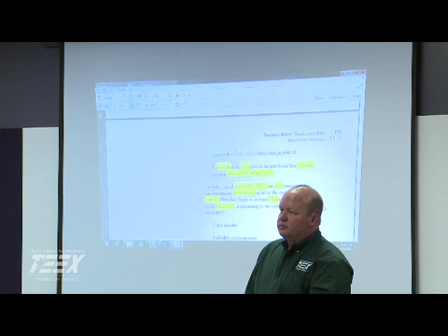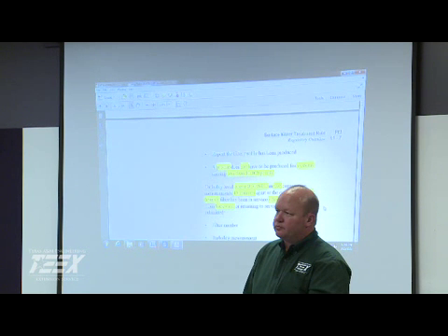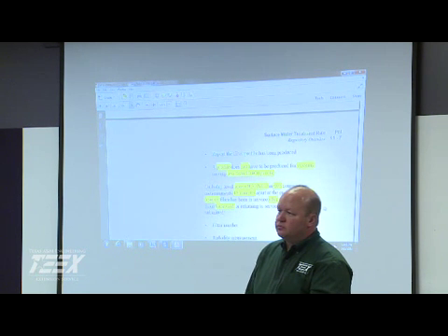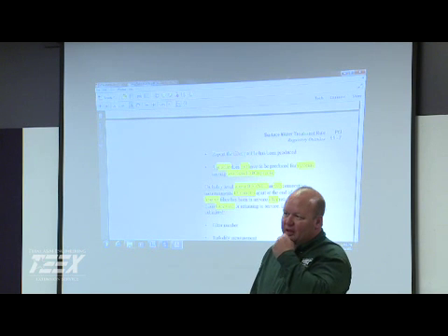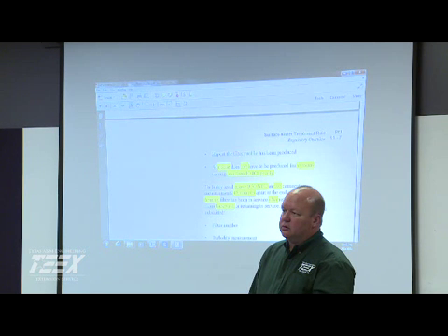Since it's been implemented, I've seen maybe 1 or 2 filter profiles, but we don't go out there and do it for them. We tell them what we'd like to see. Essentially, it's just your turbidity chart from backwash to backwash, showing where another filter's in backwash and so on.